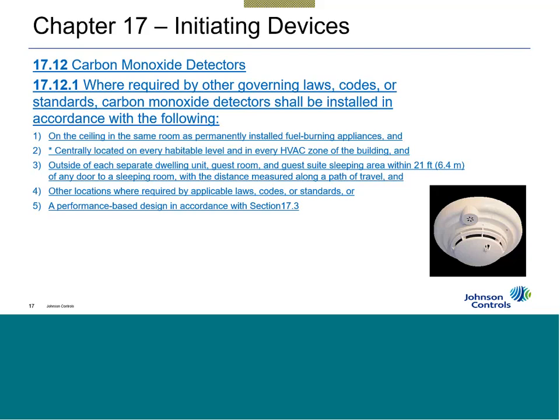So where do we put these things, since we don't have spacing requirements like we do with smoke detectors or heat detectors? The first one is on the ceiling in the same room as the permanently installed fuel burning appliance. Well, wait a minute, you just said ceiling, but you just told me it mixes freely with air. Why do you say the ceiling? Well, the key word here is burning. The characteristics of something burning makes the air that surrounds it warm. And where does warm air go? Warm air rises. The thought is, if we put it on the ceiling above the fuel burning appliance, that warm air is going to go up and take CO with it, and we'll be able to detect it as quick as we possibly can. That is the only reason it says ceiling for line number 1.